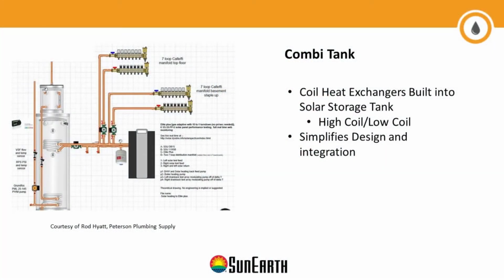For combi tanks, that's generally where we're putting the heat exchangers inside the tank itself. This is a great example. We have, again, another drain back system. It's very popular in hydronics to use drain back systems because during the summer you don't have to account for all the heat generated for an indirect system—you can drain the collectors out and avoid runaway heat on your solar fluid.